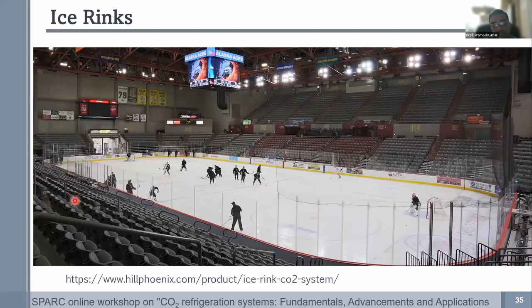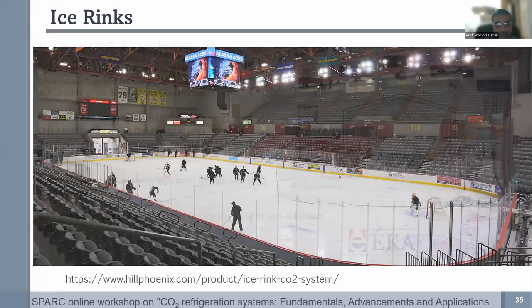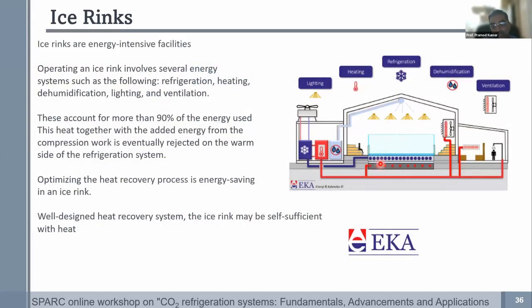But at the same time, the audience sitting around the ice rink also needs to be heated. You cannot stay at -10 or -12 degrees Celsius out here and watch the game. So you need both simultaneous heating and cooling, and this is a perfect application candidate for a transcritical CO2 system. The system has coolers that produce and maintain the ice, and at the same time the heat that is rejected is used for heating the auditorium where the audience sits. The ice rink is a classic example where both the cooling and the heating effect of carbon dioxide are efficiently utilized.